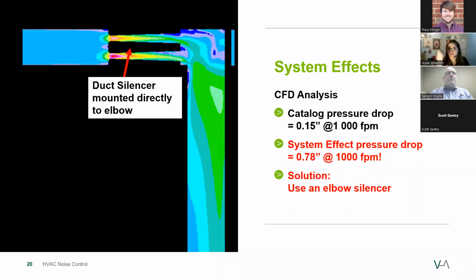So like I mentioned, when the ASHRAE guidelines or ASTM guidelines are not followed, it results in system effects, which can increase the silencer pressure drop dramatically and increase generated noise by the silencer. Here is one of the CFD analyses that we've conducted to figure out pressure drop implications. This is a side view of a duct silencer mounted directly at a duct elbow. From the start, we can see very turbulent air. The test concluded that there was an increase in silencer pressure drop and self-generated noise. To show this in numbers, this silencer has a catalog pressure drop of 0.15 inches at 1,000 feet per minute air velocity. The test measured over 5 times the catalog amount.